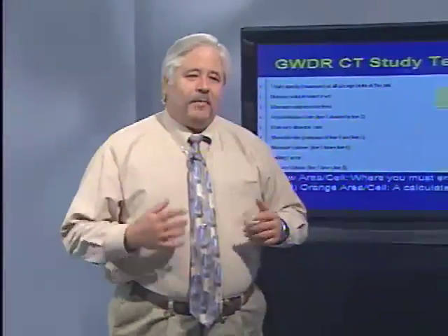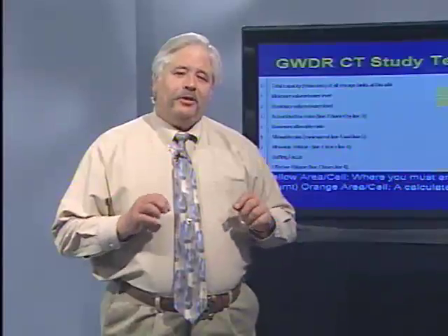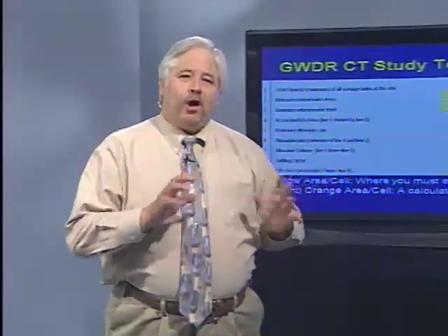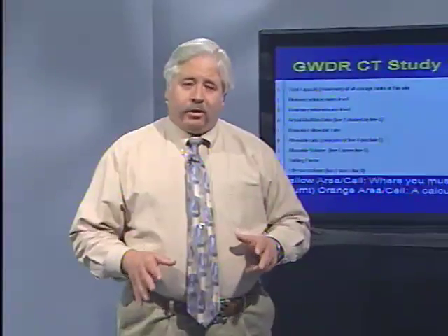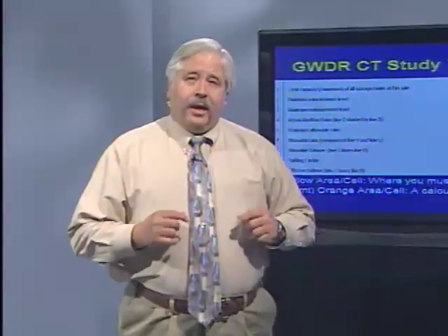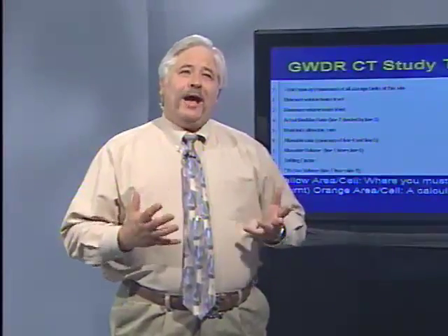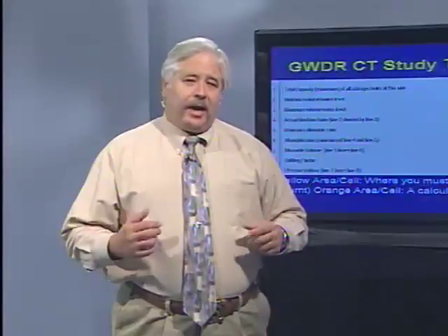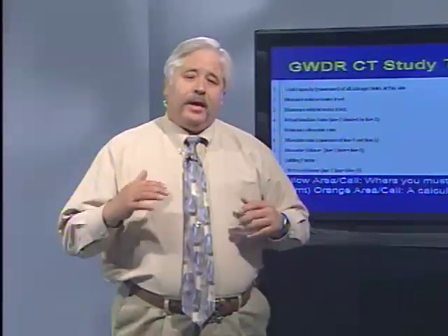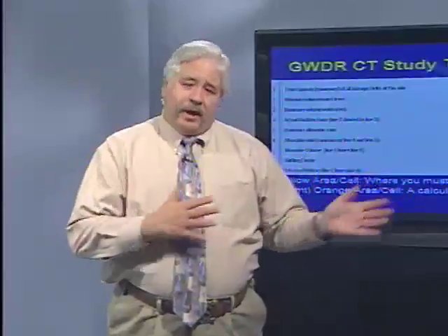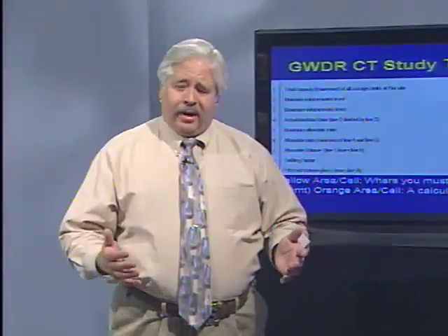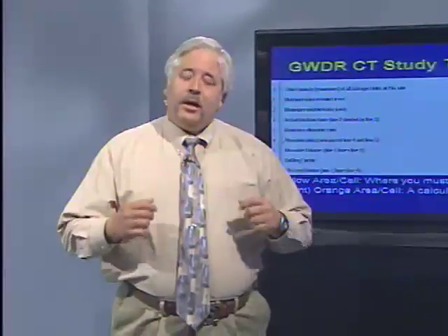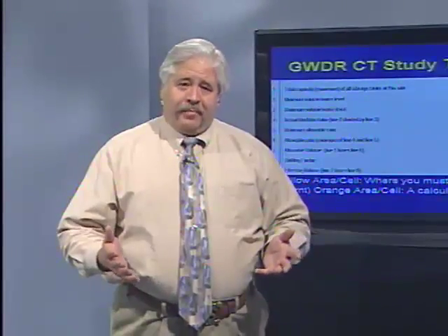Baffling factor. Baffling factor is a term used to describe, or quantify, the hydraulic short-circuiting that occurs within a storage tank. When you calculate detention time, the easiest way to think of it is the volume of the tank divided by the flow rate of water through it. So you got a 1,000-gallon tank, you got a 10 gallon per minute flow, you'll get a 100-minute detention time.